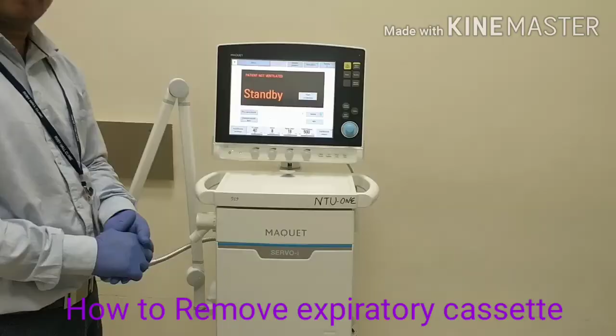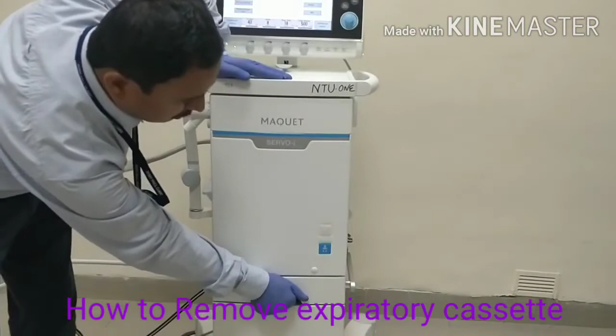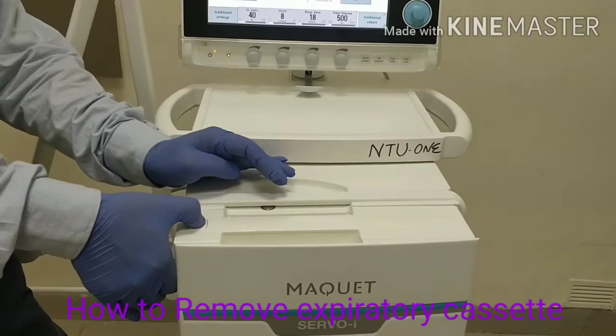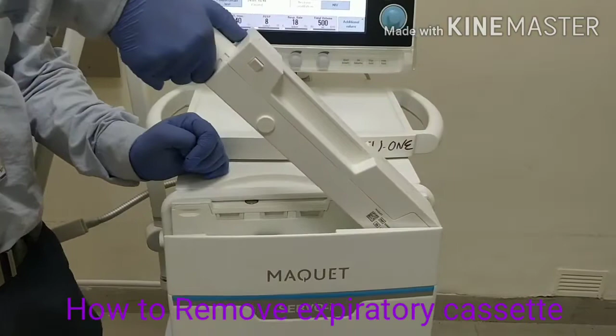Now we will see how to remove the expiratory cassette for cleaning purposes. This is the patient unit, and below it one latch is available. You just have to press it and pull out the patient unit. And here on the upper side the expiratory cassette is present. So how to remove this expiratory cassette? Keep your 3 fingers below the moisture trap, and by using your thumb just press this button, and remove it at a 45-degree angle to avoid damage to this PCB board.